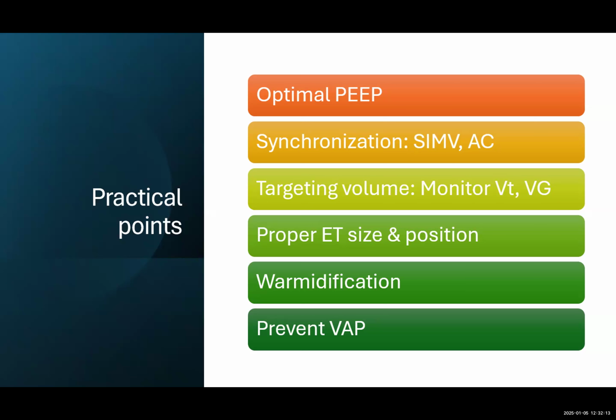Then comes humidification. If you are doing ventilation without humidification, then the biggest problem is the gases injuring the lung, and you end up giving a longer duration of ventilation, and I'm sure cold gases injuring the lung leads to the worst outcomes in the form of BPD. Currently the humidification is external, that is in the circuit, and we will see it in the workstation. But the science is so fast that in the latest generation ventilators, we have an inbuilt humidification system. That means the gas comes out of the ventilator at body temperature with proper humidity, and who knows, the whole circuit with this extension thing will disappear and we'll have a simple circuit delivering humidified gases.